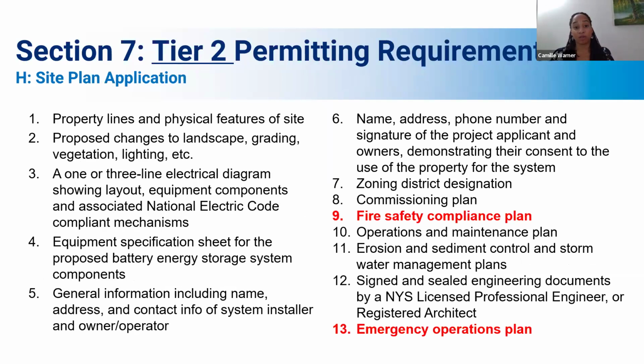The next section for Tier 2 permitting covers the site plan application—what should that look like? We recommend the standard things you'd see in any other application: property lines, landscaping changes, grading, vegetation, lighting, etc. A 1-line and 3-line electrical diagram showing shutoff mechanisms and NEC (National Electric Code) compliant mechanisms, an equipment specification sheet, contact information for the system installer, owner, operator, the name of the project applicant or owner—whoever is in charge of the system and ensuring code compliance—and what zoning district it's in, etc.